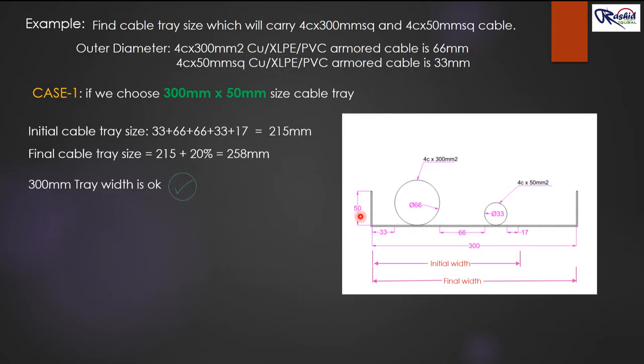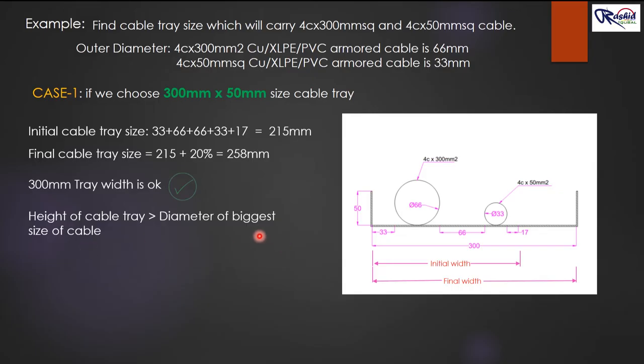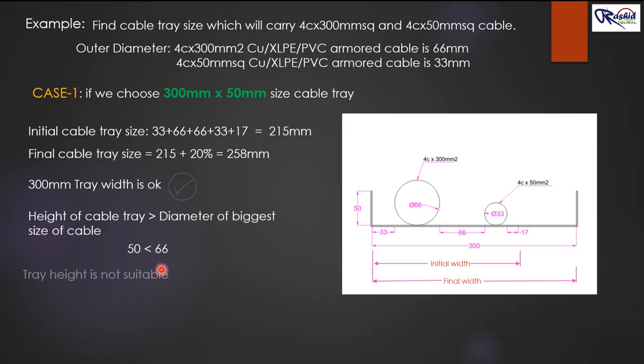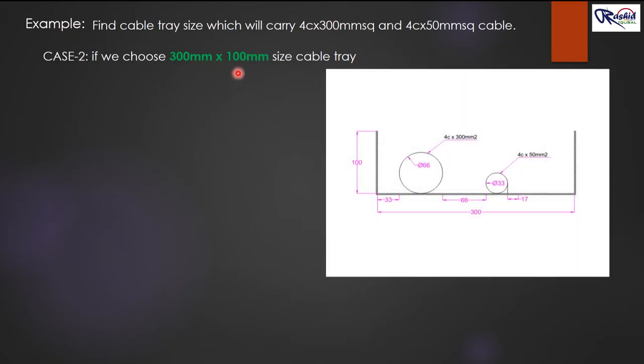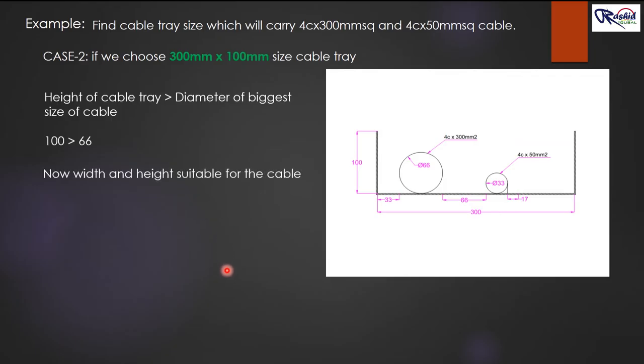Now we check the flange height. The formula is: height of cable tray must be greater than the diameter of the biggest cable. We selected 50 mm height, but the diameter of the biggest cable is 66 mm. Since 50 mm is less than 66 mm, this height is not suitable. The next available size greater than 66 mm is 100 mm. Therefore, the final selection is a 300 × 100 mm cable tray — this selection is correct.